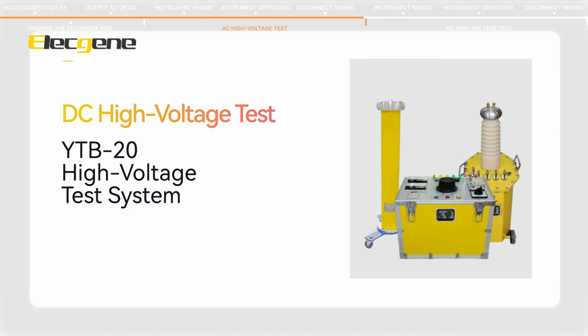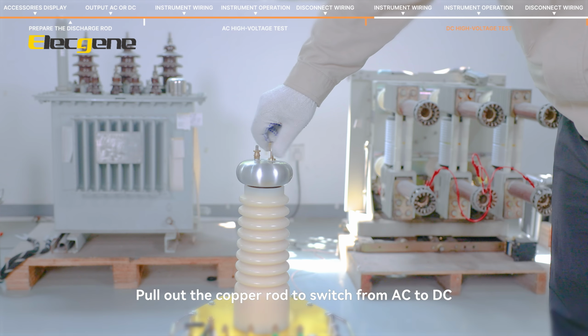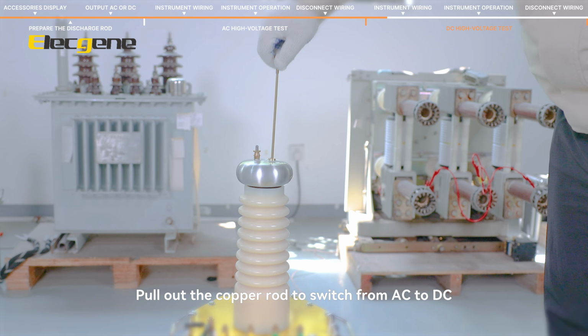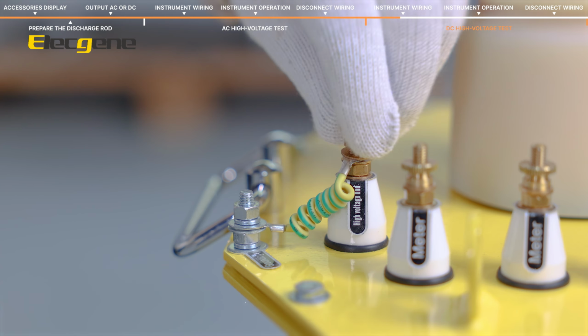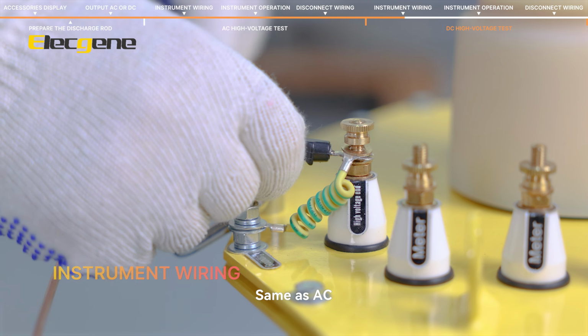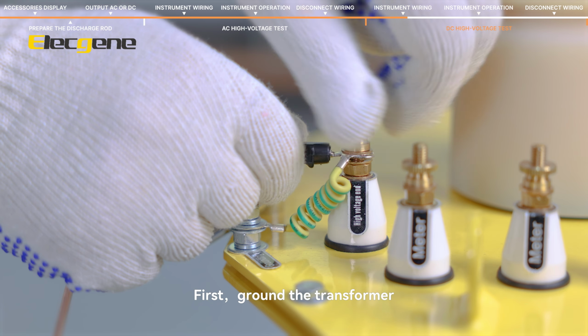DC high voltage test. Pull out the copper rod to switch from AC to DC. Instrument wiring. Same as AC. First, ground the transformer. Connect test cables.